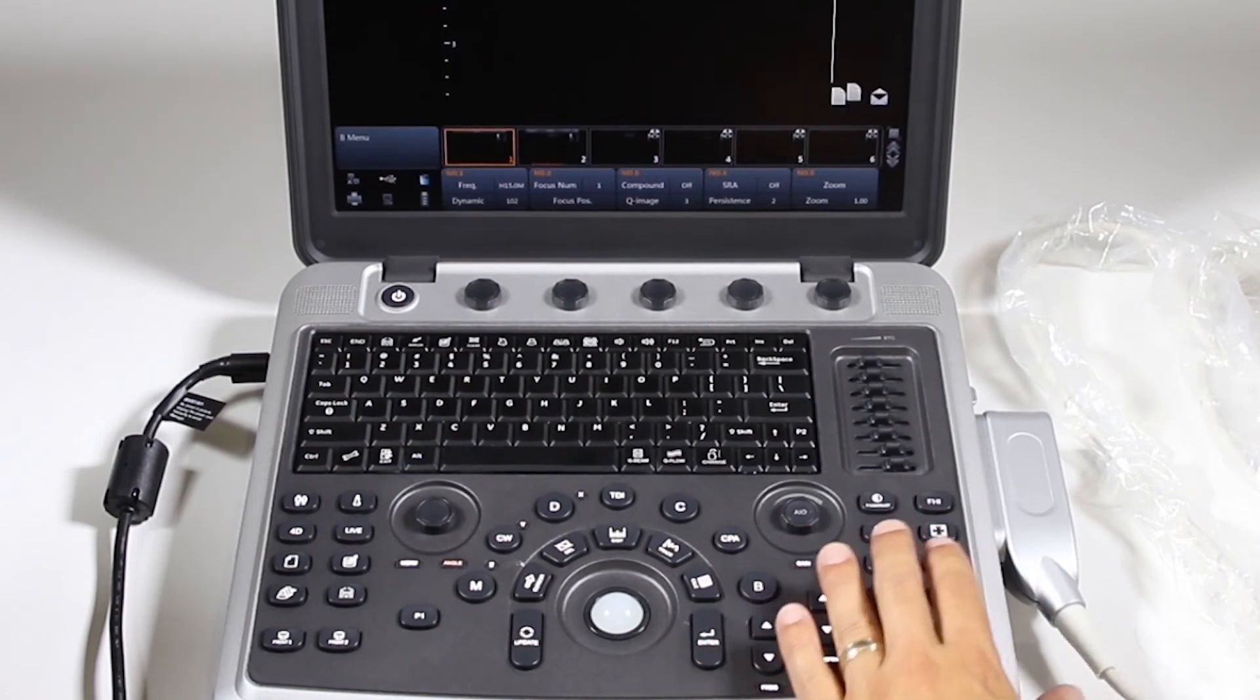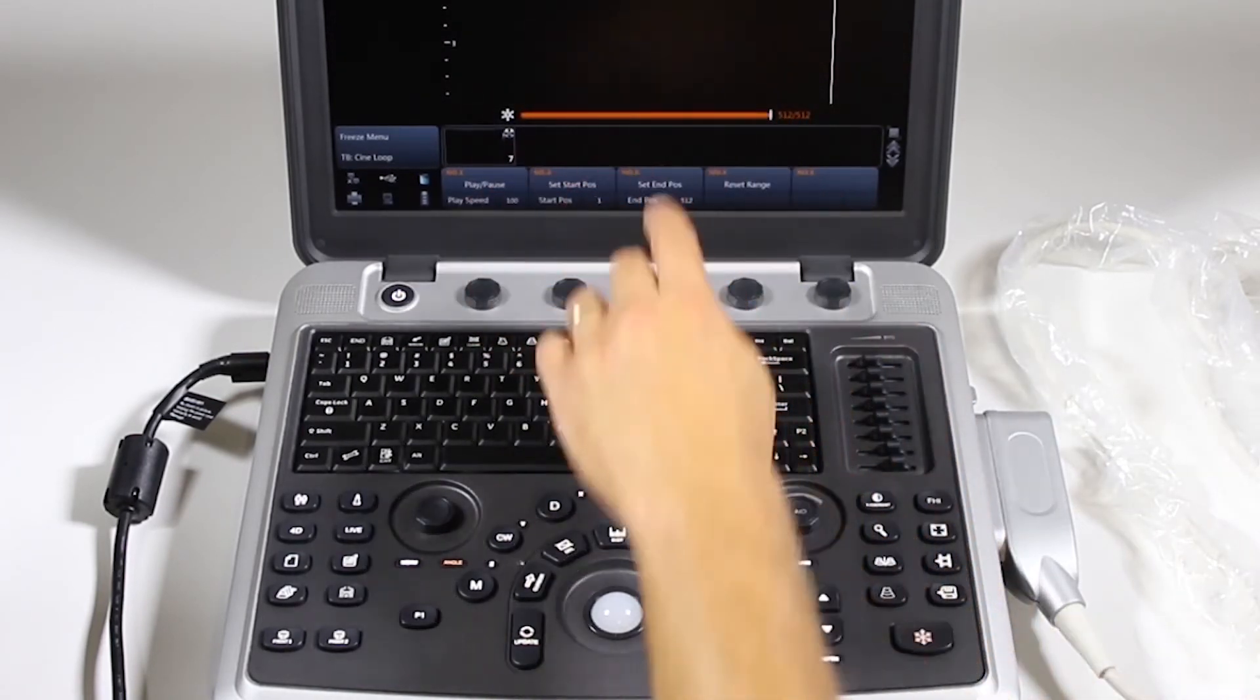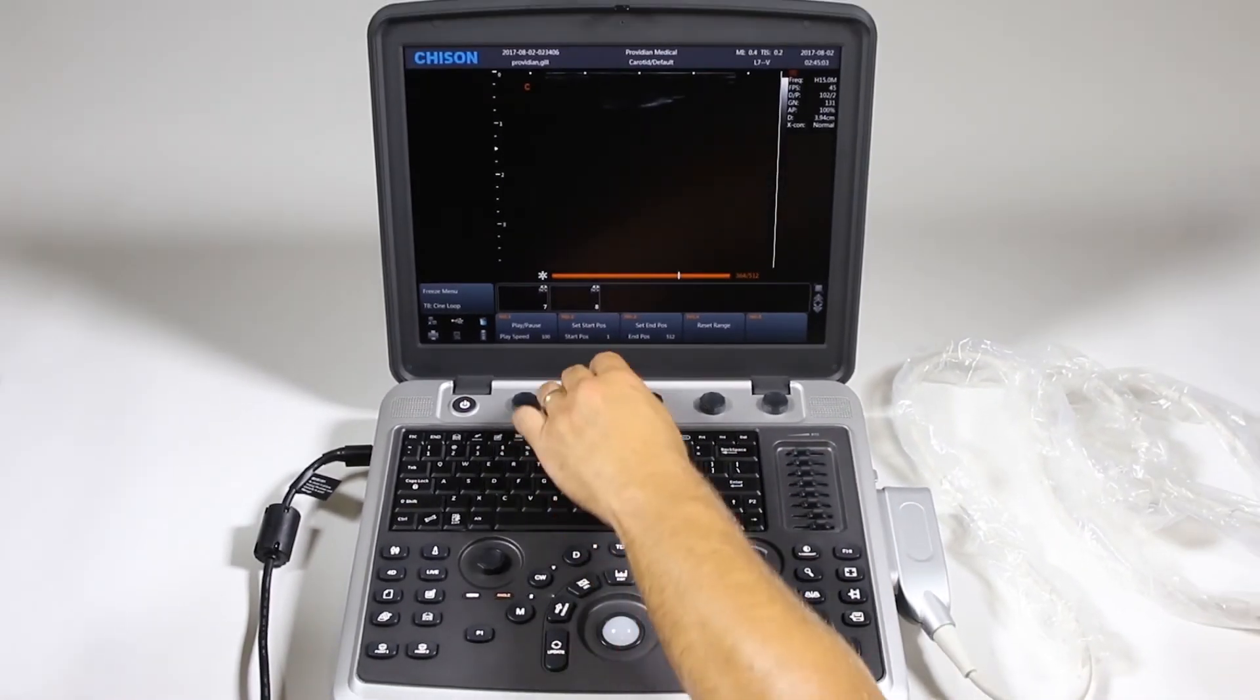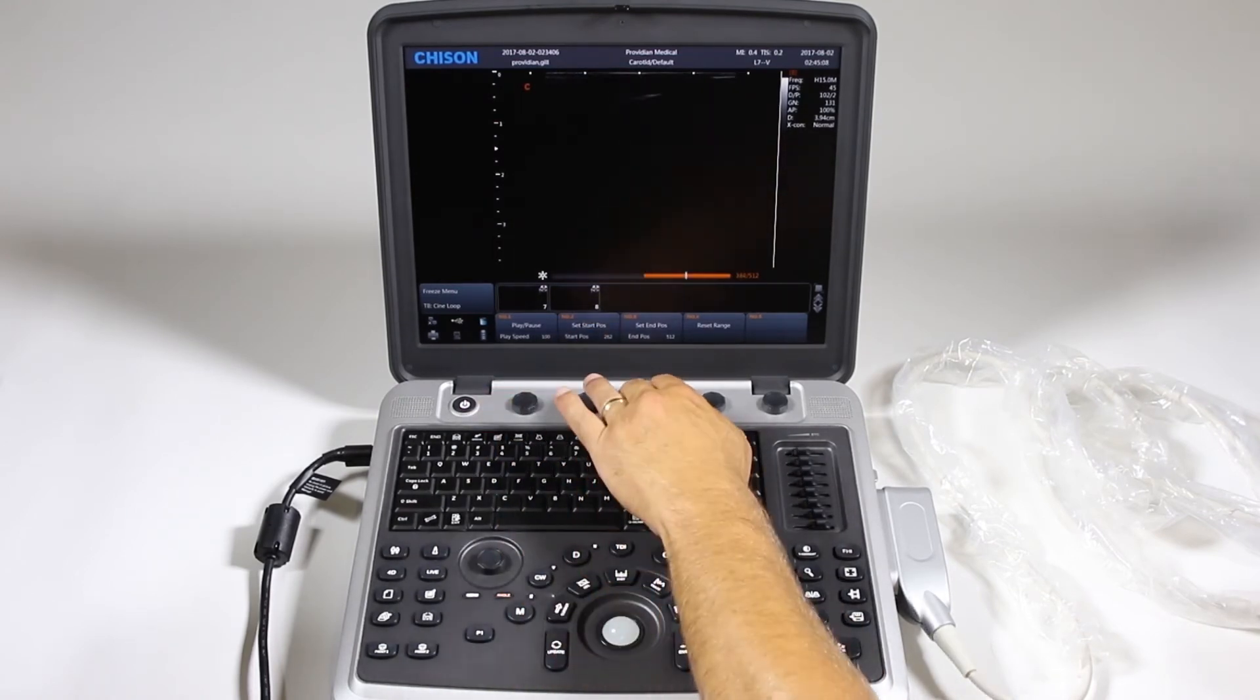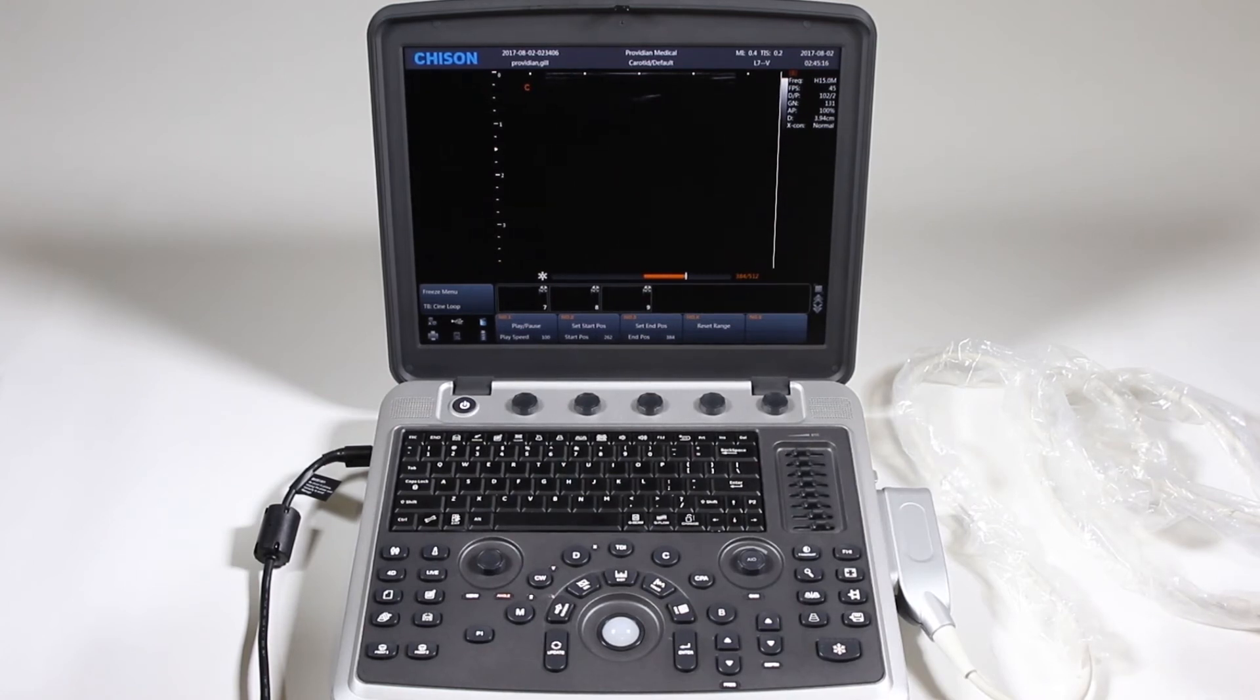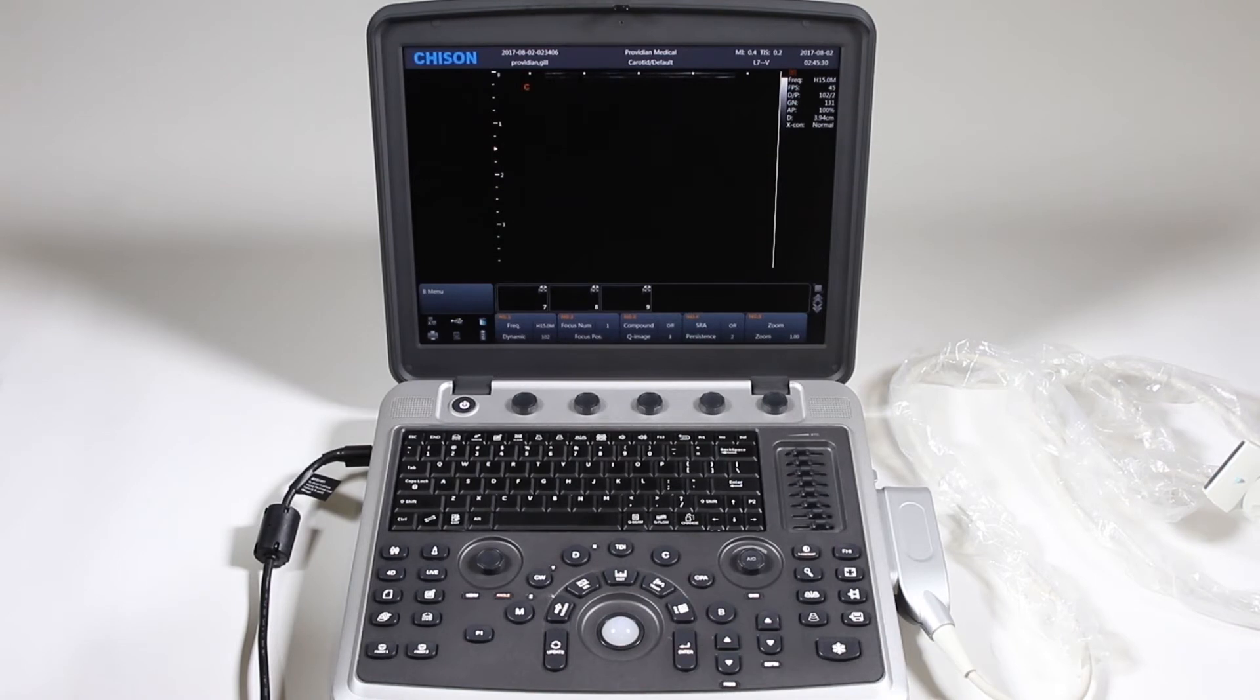So that's, this is Prospective Saving. And to go to Retrospective Saving, I'm going to freeze and it's going to show me the last 512 frames. If I want to save everything back there, I can click here and it's saved to the disk. You can also choose a range as shown in the previous. I can scroll to a spot, hit start position, scroll again, set end position, hit freeze. And it's only going to save those frames in that little loop there. So for cardiac, vascular, whatever you want to do. When you go through, if you just want to save that little portion instead of having to scroll through that entire loop later, that's a big time saver. Now if you want to do that now, it'll save you a lot of time later. Go ahead and unfreeze.